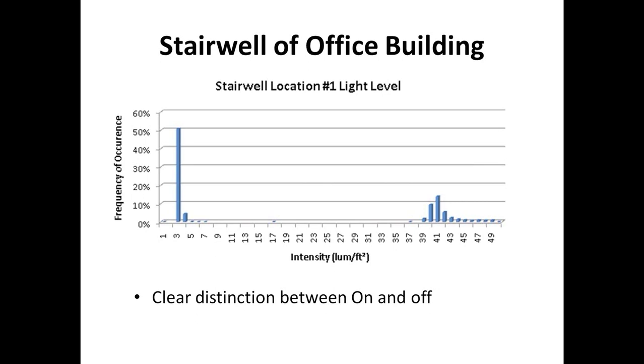There's a clear distinction between on and off. These were in stairwells where there wasn't a window, there wasn't light allowed through a window. The only lighting in these areas was from the bi-level sensors. You could see that they were actually working, that most of the time these bi-level sensors were in the low light mode, and then were responding to occupancy and kicking up to the high level mode when occupancy was high.